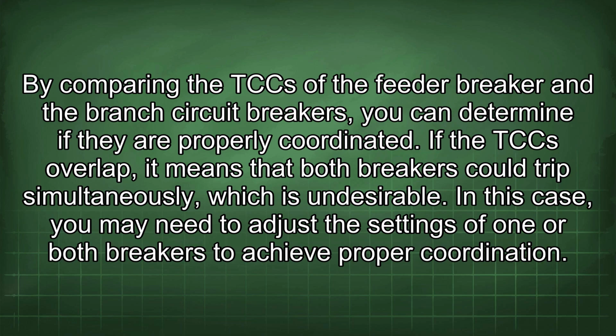By comparing the TCC of the feeder breaker and the branch circuit breakers, you can determine if they are properly coordinated. If the TCCs overlap, it means that both breakers could trip simultaneously, which is undesirable. In this case, you may need to adjust the settings of one or both breakers to achieve proper coordination.